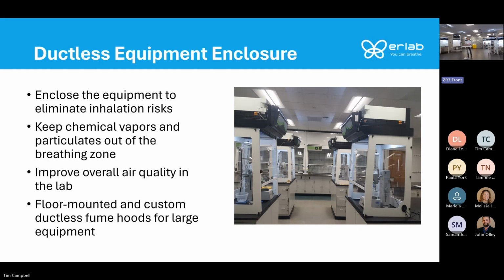So think about it. If you have equipment, you can isolate it. So you can put it in the enclosure, which isolates the worker from the hazard, which is always the best step. If you can reduce any of the chemical vapors from being released in the lab space, be contained in a fume hood, and then the chemical vapors or particulates being generated within the enclosure, captured by the filtration. We have floor-mounted models available through Labconco. We also have a partner who can custom make just about any size hood you want to match any type of equipment you may use.